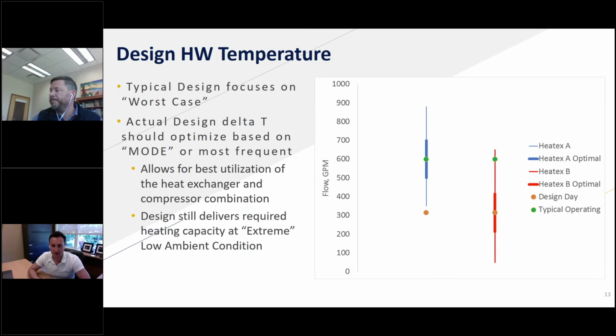A couple more. At low ambient temperatures, can you truly get a fully electrified heating system? The person asked, from my understanding, the system requires supplemental electric heat or some sort of supplemental heat to defrost. So for New York, you definitely can have a fully electrified building with air source heat pumps. Where I live, it gets to be -30. I would say you cannot have a fully electrified building at -30 simply with air source heat pumps. There are other ways of electrifying that building with a hybrid solution that we would talk about. But in New York, you certainly can do it.